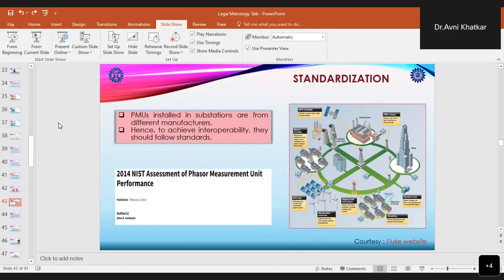Now, when we talk about PMUs, we will have to see their standardization also, how they are standardized. As these PMUs are installed in the grid, in the substations, they are not all from the same manufacturer. They are from different manufacturers and they provide data. So in order to achieve interoperability and to have PMUs which follow the standards, this standardization of PMUs came into the picture. As they are installed in the utilities, they provide the phasor data. So first of all, organizations like NIST develop tests in order to characterize the PMUs and qualify them for service.